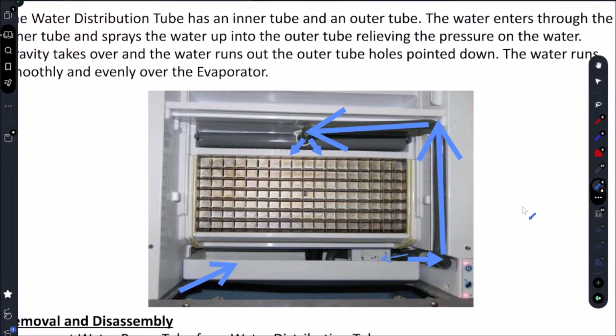So at this point, there are a few reasons why we might experience a max freeze of 1 hour. First things first, is our pump, which is located right here, circulating water through the manifold and onto the coil? If that's working, the next thing is, is our coil actually getting cold? If it's not getting cold, then we go to that 10% issue I mentioned of there being a refrigeration issue. But like I said, it's very rare we're going to get a refrigeration issue on an ice machine.